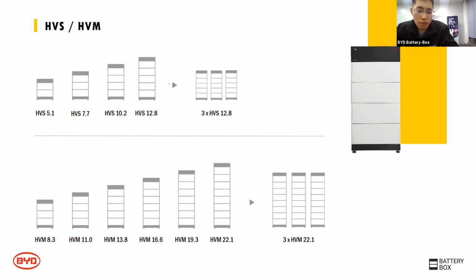For HVM, the minimum battery number is 3 modules, giving a capacity of 8.3 kWh. This has a very significant capacity — you can stack up to 8 modules in one tower, about 2 meters high, giving about 22 kilowatt-hours. You can also parallel 3 towers, giving a maximum capacity of 66 kilowatt-hours. It's a very big capacity.